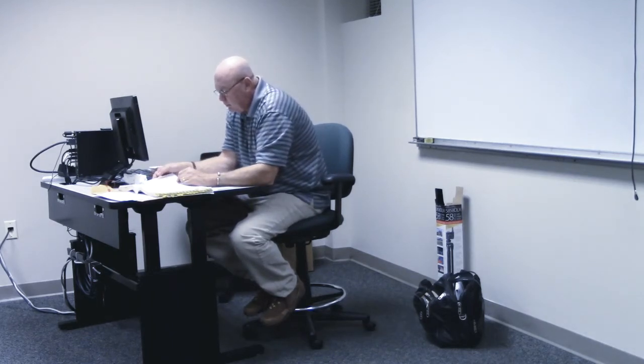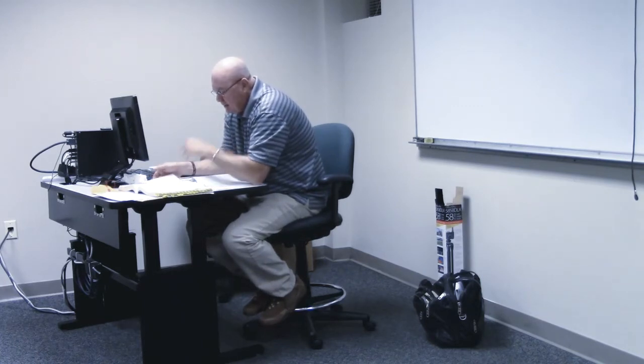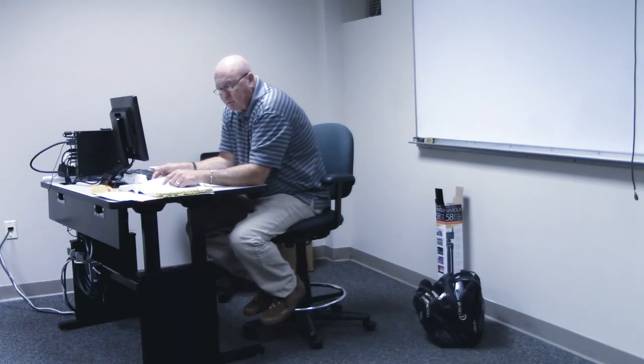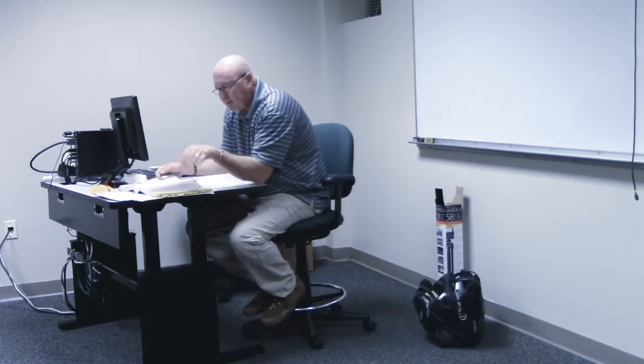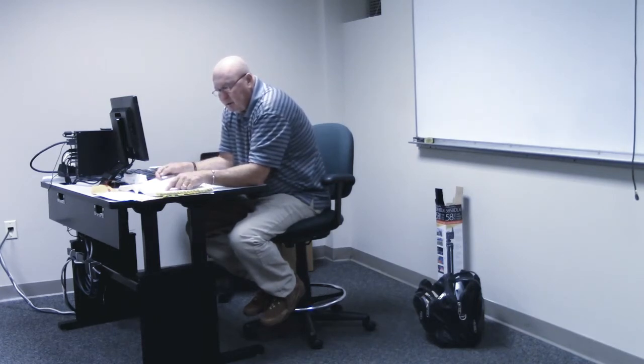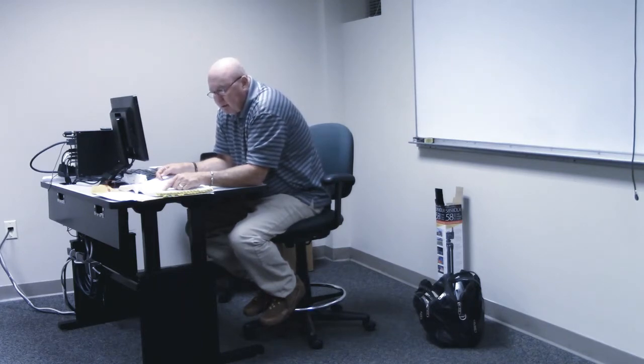So 501.130B is actually talking about Class 1 Division 2, isn't it? No, I'm sorry. Yeah, 130, yeah. And we see here, under luminaires, where lamps are of a size or type that may, under normal operating conditions, reach surface temperatures exceeding 80 percent of the auto-ignition temperature in degrees Celsius of the gas or vapor involved. We'll have to find out what that is in a minute. Luminaires shall comply with 501.130A1 and shall be marked, type to be tested in order to determine the marked operating temperature.